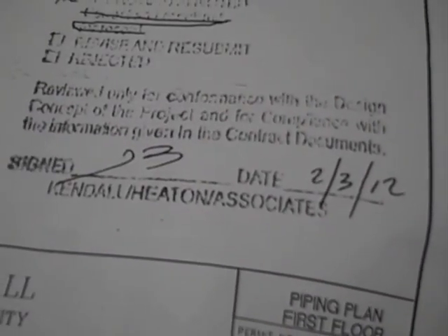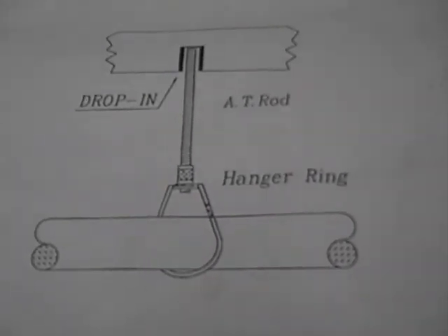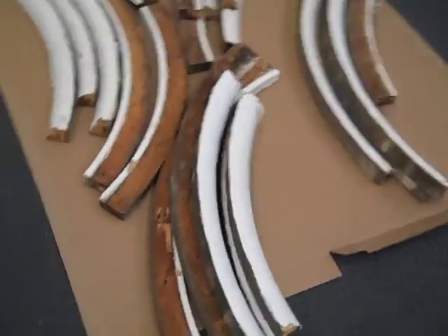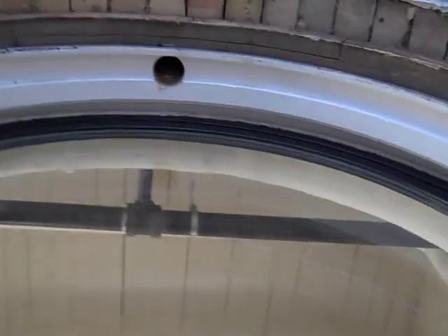Rather than replace a few of the 3/4 hour glazing panels with 1-hour fire-rated glass, a simple solution which would have solved that particular problem, the architects decided to instead rebuild a number of the non-compliant openings by adding special sprinklers on either side of the 3/4 hour rated glazing panels. This required first removing the existing window and trim, drilling holes in the masonry for the sprinkler pipes, and then installing the sprinkler heads. In the end, the fire barrier wall was still non-compliant since the specifications for this special sprinkler system were not met, but that's another story.